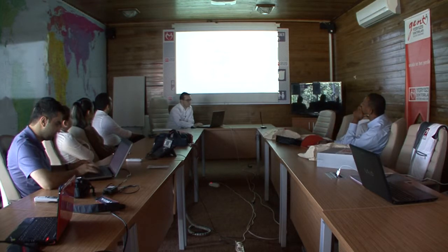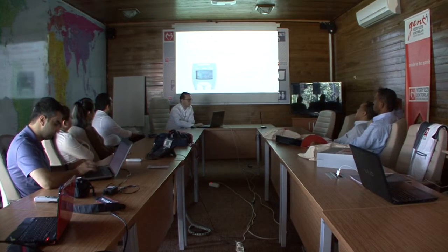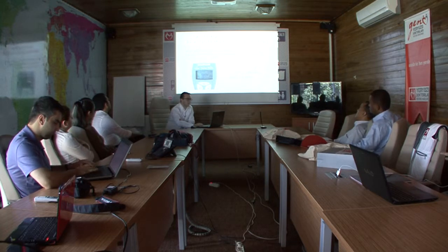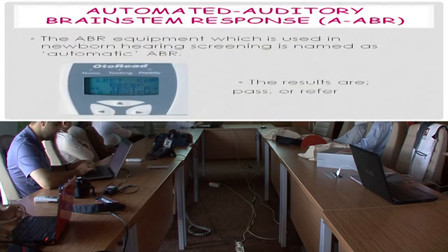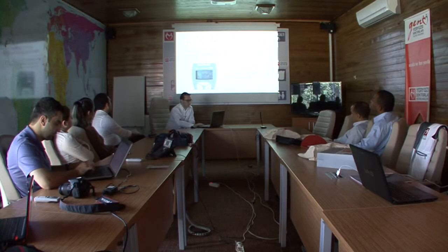The click stimulus generates a response from the hair cells of the cochlea, and this signal travels along the auditory pathway from the cochlear nerve to the midbrain. This electrical activity is measured by electrodes placed onto the scalp, and this is the basis of the test. The ABR equipment used in newborn hearing screening is named automated ABR because these devices use standard and fixed test protocols, and the results are given as passed or referred — not detailed results.